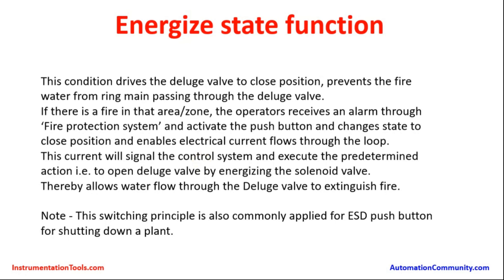The push button is in open position during normal conditions, but whenever there is a fire, the operator pushes the push button. There could also be some automated actions through the fire protection system. During that condition, current flows through the push button and through the solenoid valve. This current signals the control system and executes the predetermined action — that is, to open the deluge valve by energizing the solenoid valve. Water then flows through the deluge valve to extinguish the fire.